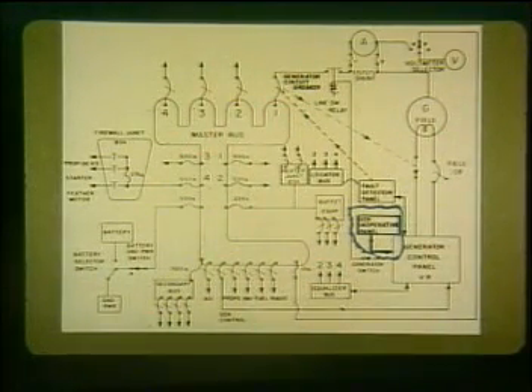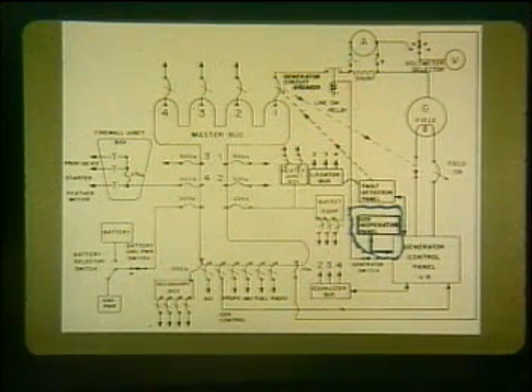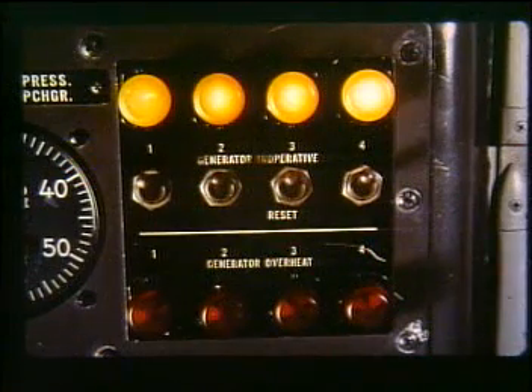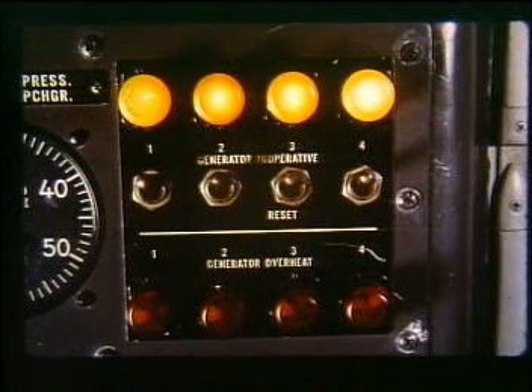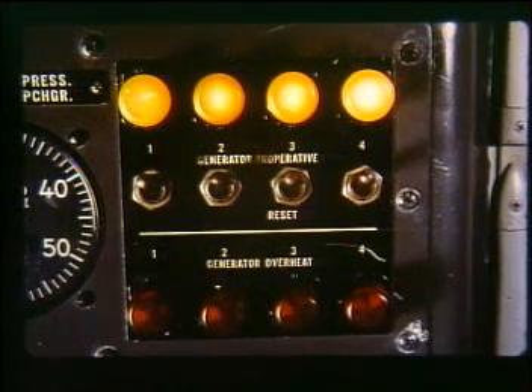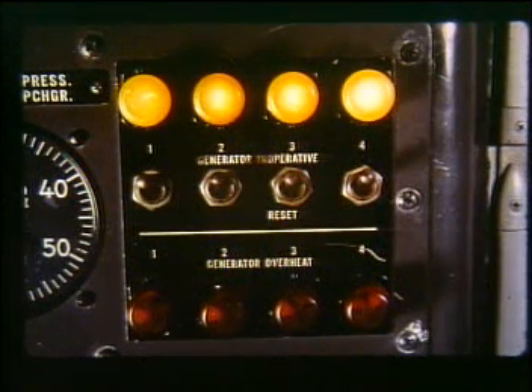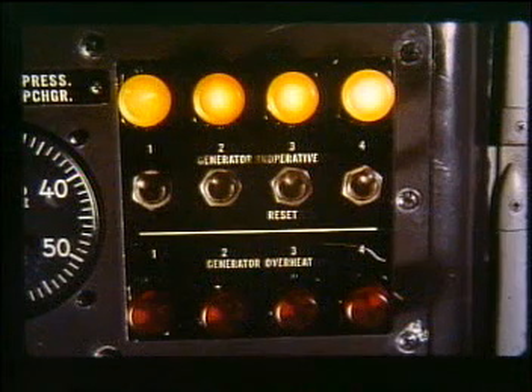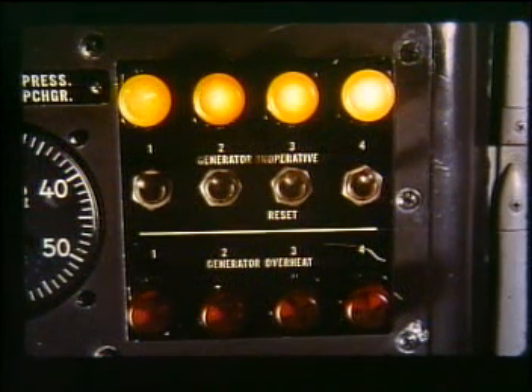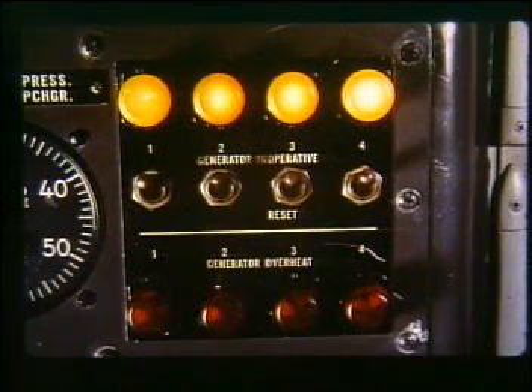The generator inoperative panel, outlined in blue, is located above the generator ammeter voltmeter panel, to the right of the duct pressure gauges. Here are the 4 red overheat warning lights, located on the bottom of this panel, giving the overheat warning from the generator PlugStat. Located just above the warning lights are the 4 momentary toggle-type reset switches that will electrically reset the generator circuit breaker. Above the reset switches are 4 amber generator inoperative lights that will illuminate whenever a generator is not on the bus.